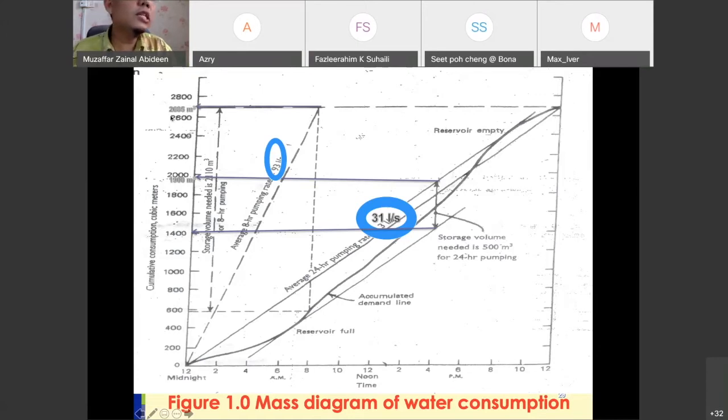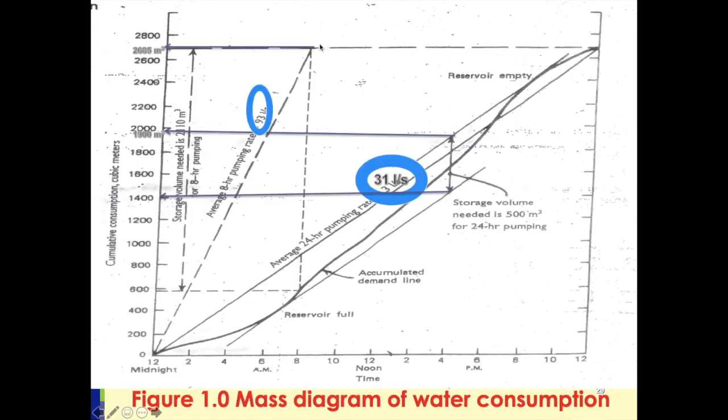The max value is 2685 meter cube. That means within these eight hours, from 12 o'clock midnight until eight o'clock in the morning, they've got to pump the water so that by eight o'clock in the morning, the storage reservoir has already had 2685 cubic meter of water. So that's why they need to pump really quickly, to achieve this level or to achieve this volume.